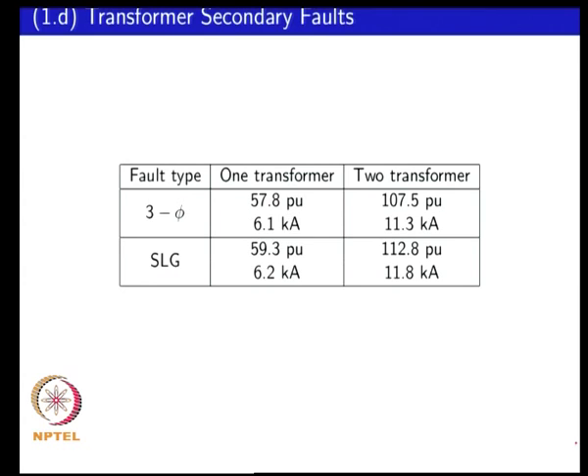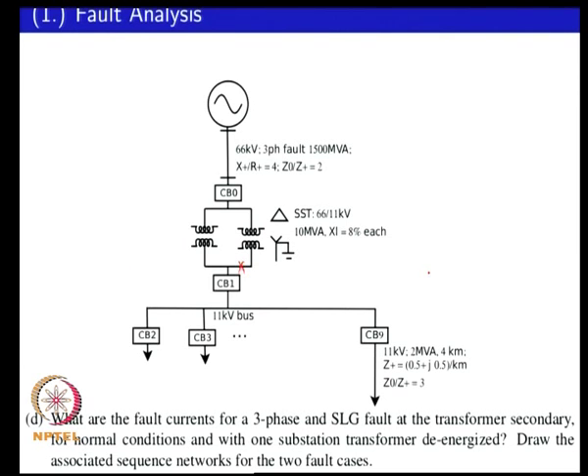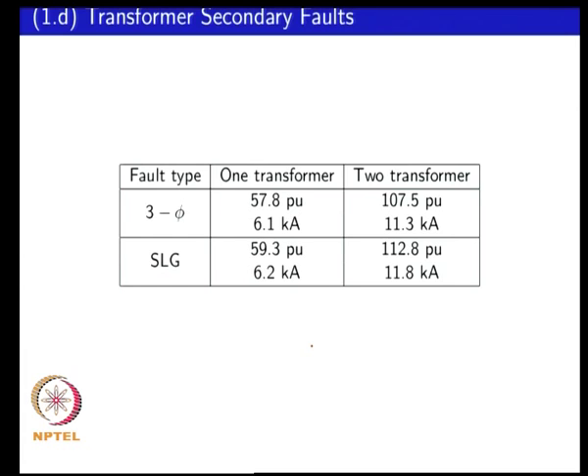You can see that when there was one transformer, if you have two transformers the fault current level is almost double. You can still see that the single line-to-ground case has higher current. So if you want to protect circuit breakers for a fault occurring on the low-voltage bus of the substation, you need to rate your system to handle the highest level of fault current, which happens when both transformers are operating in parallel.